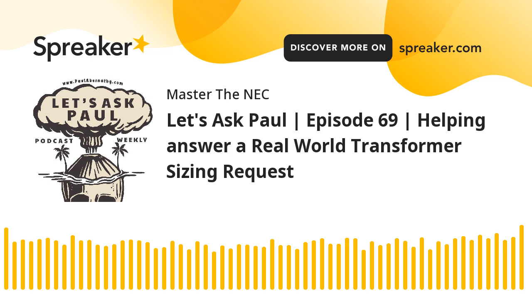Well, right now that's a 100 amp rated device, and those conductors are rated for 85 amps, a number 4. Remember, they're on the line side of the protection for the HVAC, the disconnect, which is 100 amp rated.